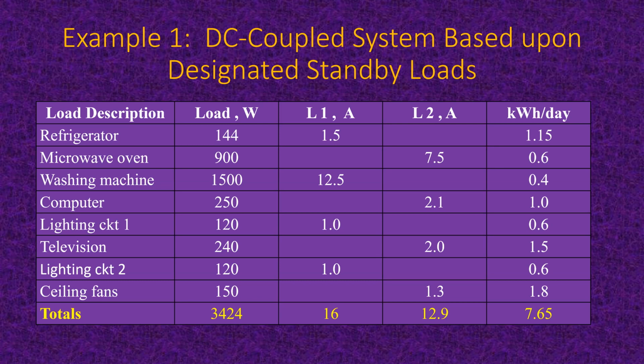And so everybody can read the table here. What we're looking at is the totals that are important. The total load in watts is 3,424 if everything is on at the same time, and we need that in terms of the power rating of the inverter. The maximum current on line 1 is going to be 16 amps. Maximum current on line 2 is going to be 12.9 amps.